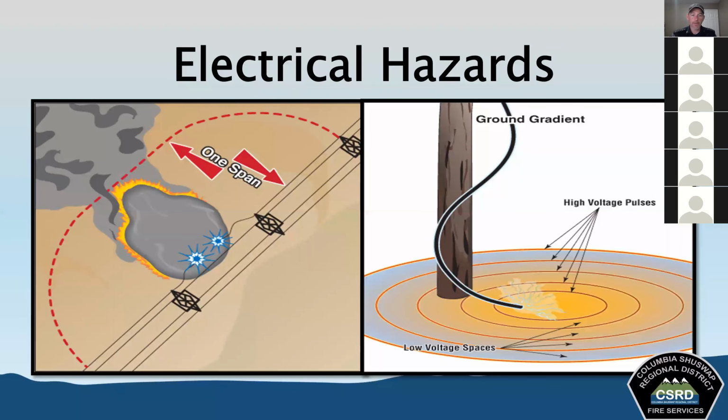the electrical current takes through the body, the degree of resistance, and that includes the resistance of our skin. If it's wet, we have very low resistance. If it's dry, it might be a little bit higher. The length of our exposure to the electrical current. What's the available current, the amperage flow? And the available voltage, which is the electromotive force. And then what frequency is it? Are we talking about alternating current or direct current? That's all going to affect the seriousness, but the one thing that's certain is we don't want to be coming in contact with electricity.